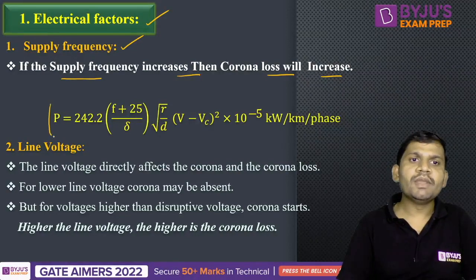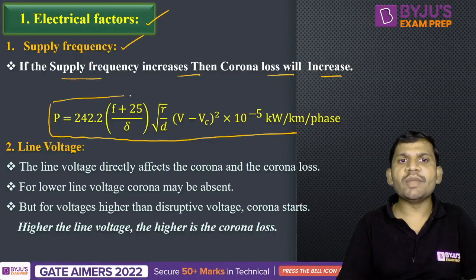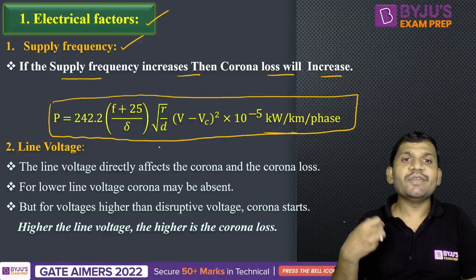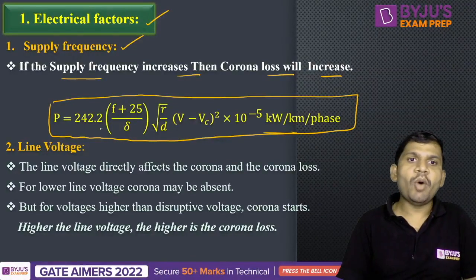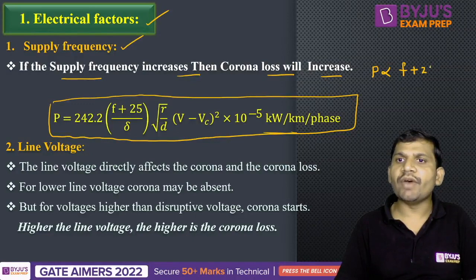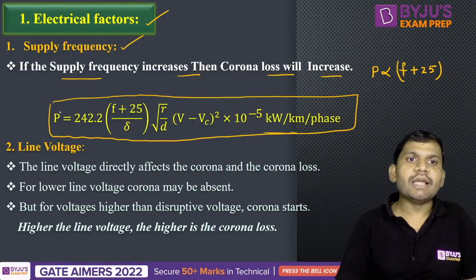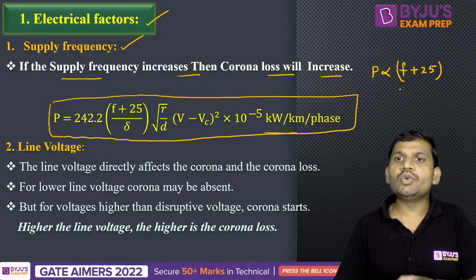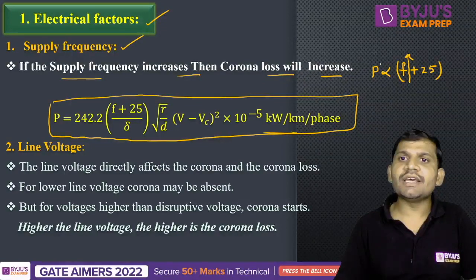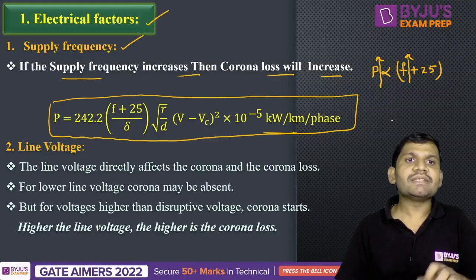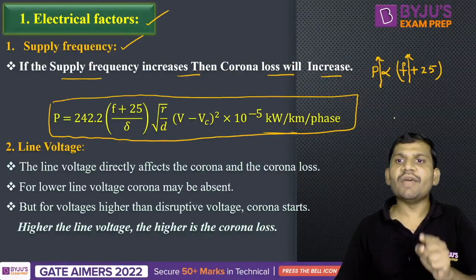This is one important formula: the power loss due to corona, P, is proportional to (f + 25). This is a very important formula to solve problems also. The corona loss, that is the power loss, is proportional to (f + 25). If the frequency increases, then the power loss also increases. This is how the supply frequency affects the corona loss.